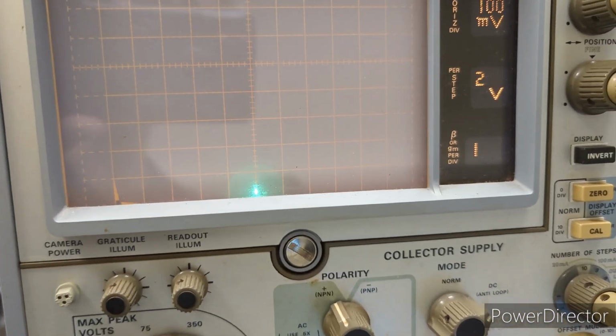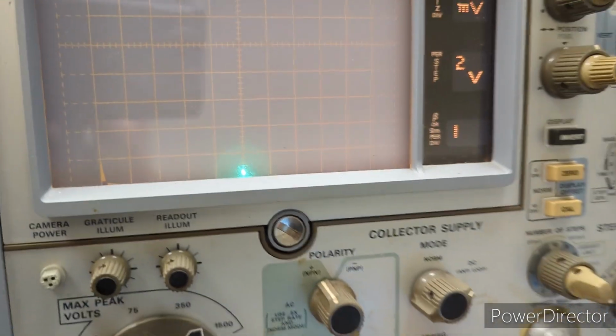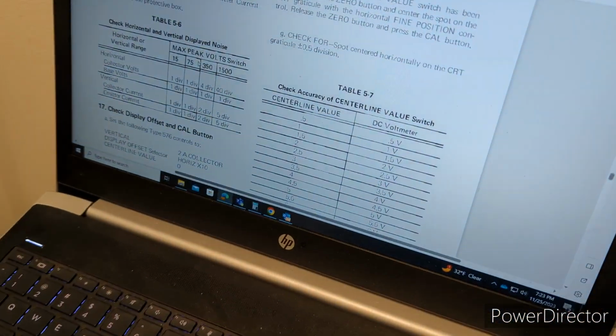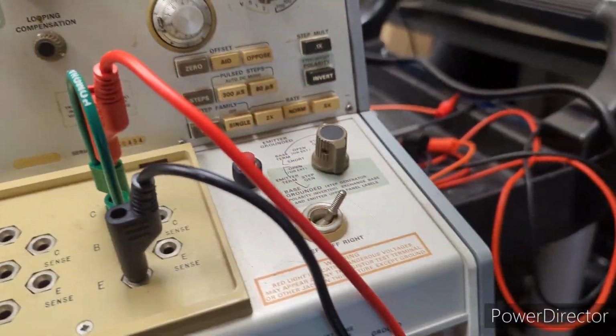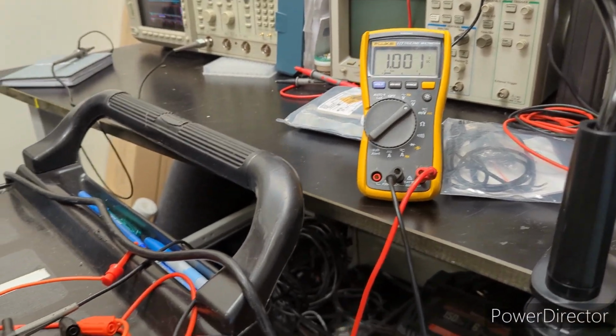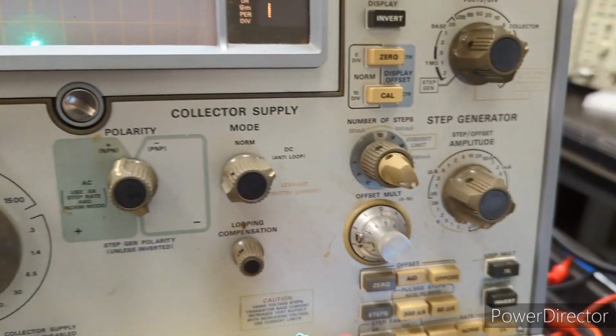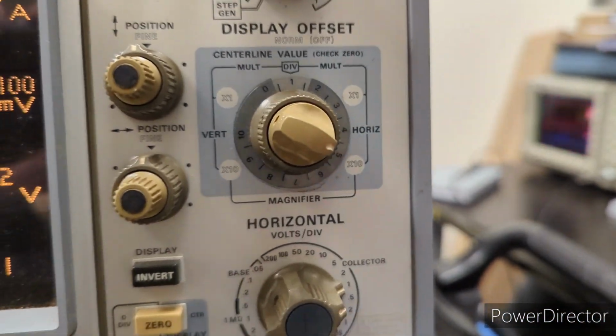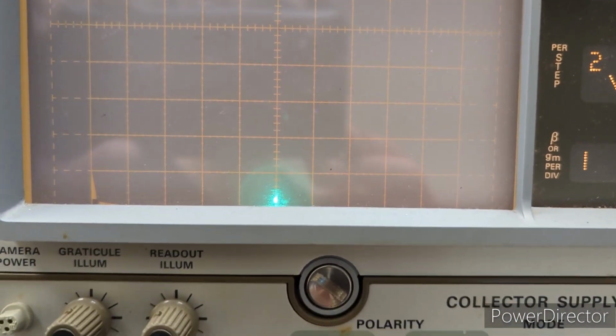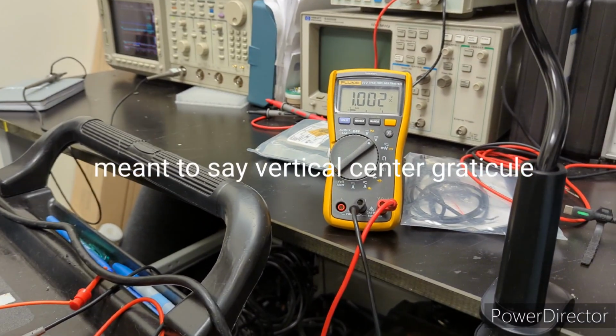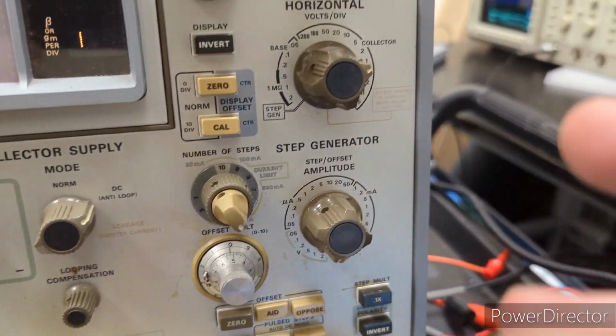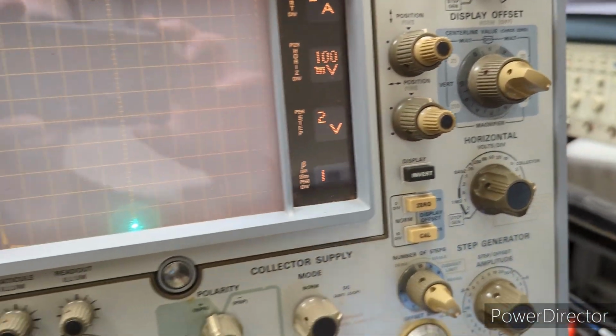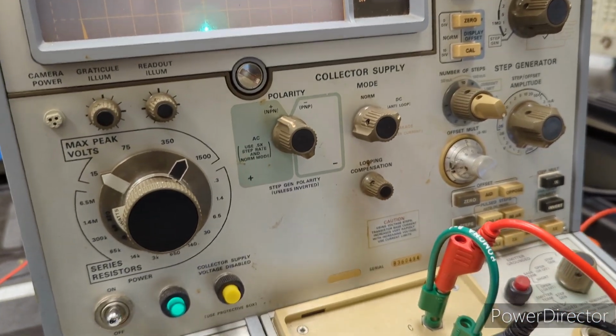Okay, so this is another step that we weren't able to perform, or at least get the correct results of. This is checking the center line value switch accuracy. When we did this the first time in my third video, we weren't able to do it, but now you can see clearly on the meter we've got 1 volt, and we are getting that voltage using the offset multiplier switch. Also, we've confirmed that the center line value switch is accurate. We have it set to 1, the trace is centered on the CRT reticle, and we have 1 volt on the meter. I'm going to do that for each setting of the center line switch, and make sure it's accurate for each setting.